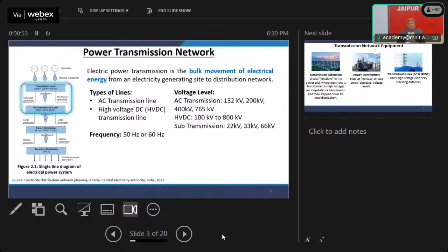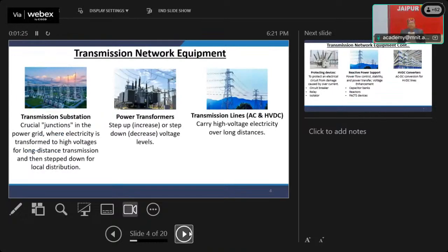You could see the AC transmission takes place at 132 kV, 200 kV, 400 kV, 765 kV. And also, we may have HVDC networks, which are of 100 kV to 800 kV. Sub-transmission, 22 kV, 33 kV, and 66 kV, is nothing but the joint between distribution system and transmission system. The frequency across the world may be any frequency, but mostly it is 50 or 60 hertz. Transmission network equipment very commonly seen includes transmission substations, power transformers, and transmission lines.